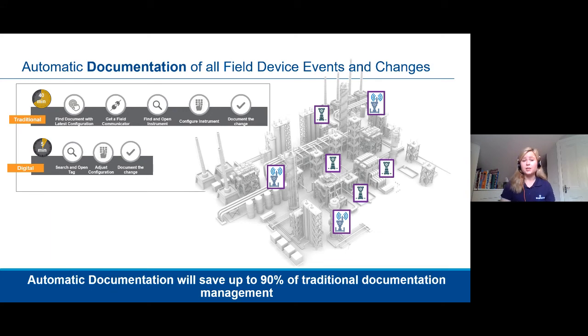So traditional maintenance was done with a field communicator by doing an awful lot of prep work and following these steps once out in the field. Digital maintenance makes it so much easier. You search for your device tag, you do the changes, and then the changes are automatically documented, all online, time and date stamped with who did what and why.